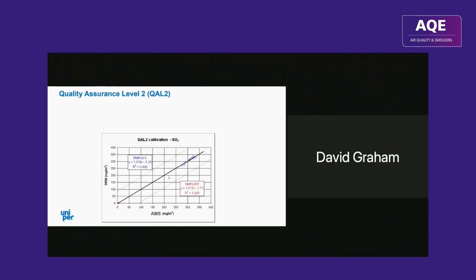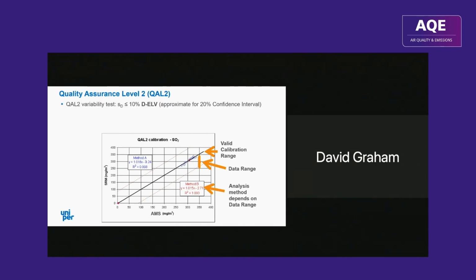So moving on to Qual 2. This is the straight line calibration between the test method as operated by the accredited laboratory and the plant monitor, the AMS. This is a rather idealized set of results showing almost one-to-one agreement, which is what you would hope for. The valid calibration range is 10% higher than the highest reading. The min-max data range determines which method of analysis is used, but this is simply whether you include all the points in a linear fit or just average them into a single red dot up here and then pass it through zero. And there's no absolute requirement for the SRM to agree with the AMS.